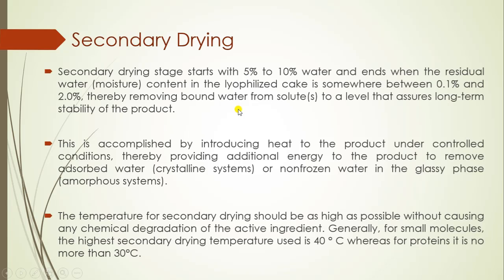Secondary drying starts with 5 to 10 percent water and ends when residual moisture contained in the lyophilized cake is around 0.1 to 2 percent, thereby removing bound water from the solute to a level that assures long-term stability of the product. This can be done by introducing heat to the product under controlled conditions, providing additional energy to remove adsorbed water in crystalline systems and unfrozen or bound water in the glassy phase, that is, in amorphous systems.